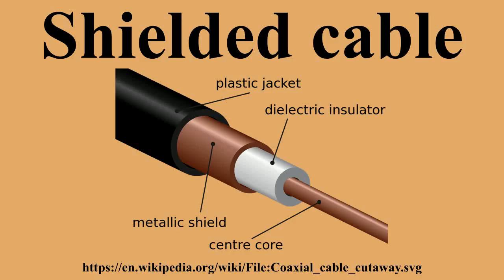Signal cables. The best method to wire shielded cables for screening is to ground the shield at both ends of the cable. Traditionally, there existed a rule of thumb to ground the shield at one end only to avoid ground loops. In airplanes, special cable is used with both an outer shield to protect against lightning and an inner shield grounded at one end to eliminate hum from the 400 Hz power system.